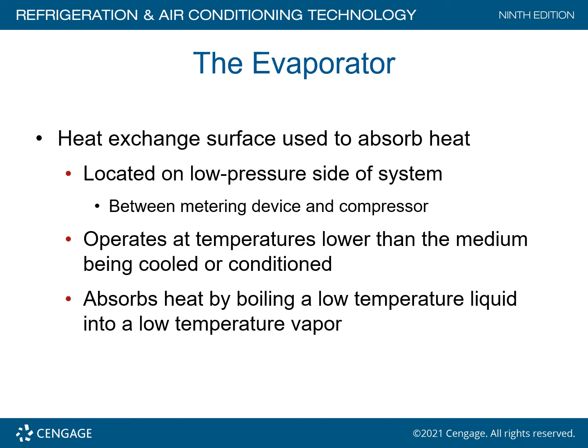Now I need to say this about evaporator coils. If you don't have the proper airflow across that evaporator coil, it's going to freeze up. If the evaporator coil is filled up with dirt, it's going to freeze up. And your ability to extract heat from a product or from the air is reduced correspondingly based on the amount of dirt or lack of airflow. It is critical to keep the airflow at a correct level, and it is critical to keep that coil clean. If the coil is not clean, your ability to extract heat is impacted. Bottom line.